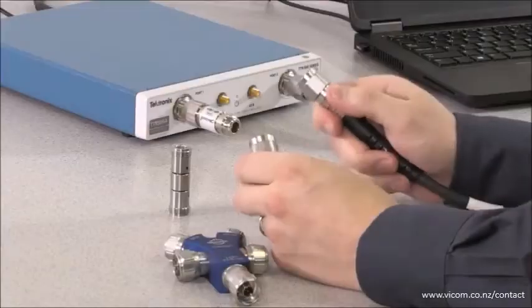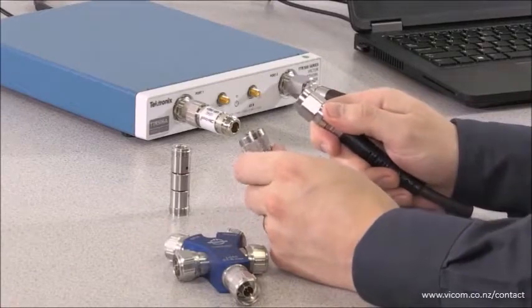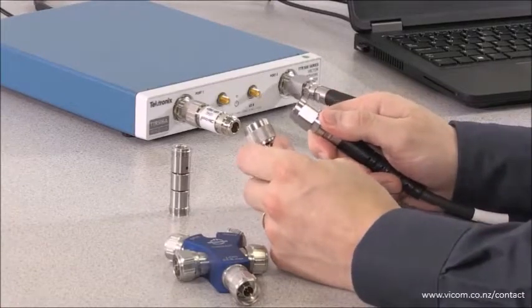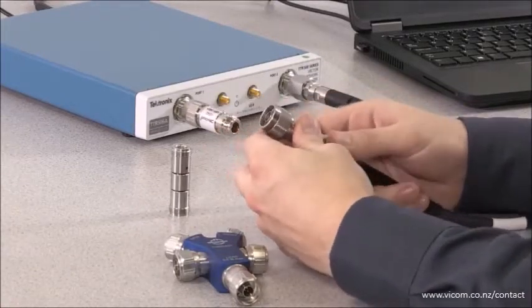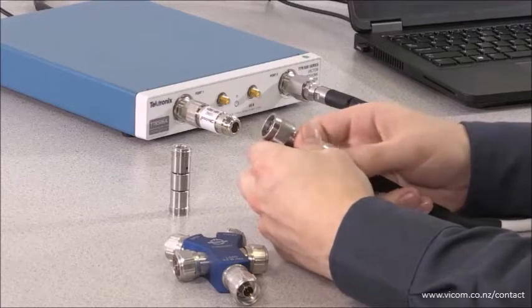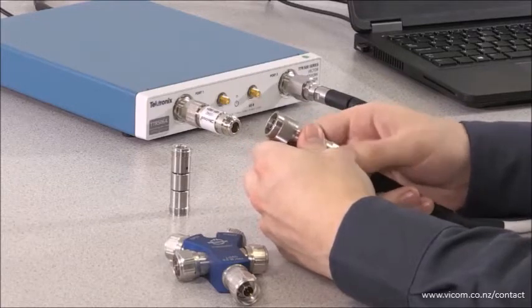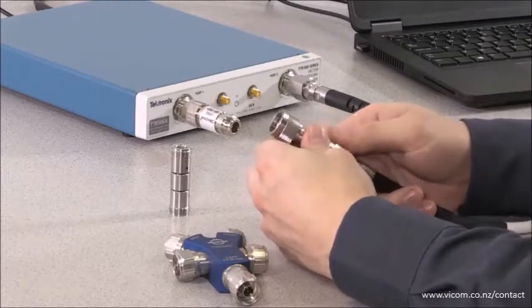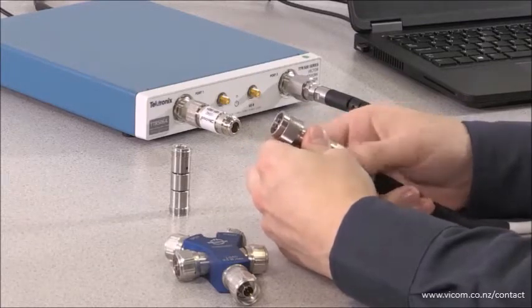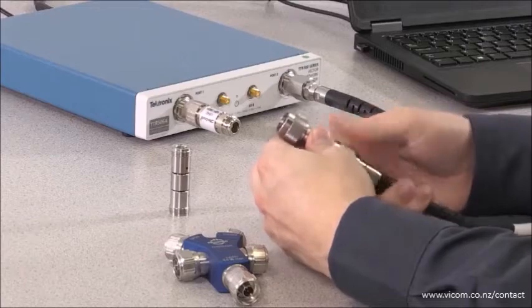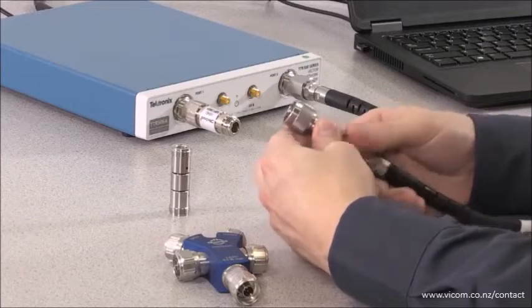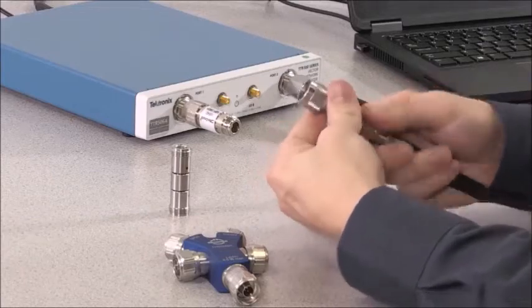We first need to determine the delay attributed by the male-to-female adapter. To do this, connect the female-to-male adapter to port 2, the cable on port 2, and to port 1 of the VNA.